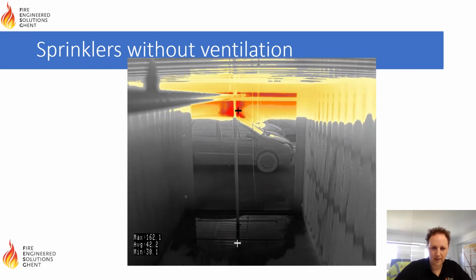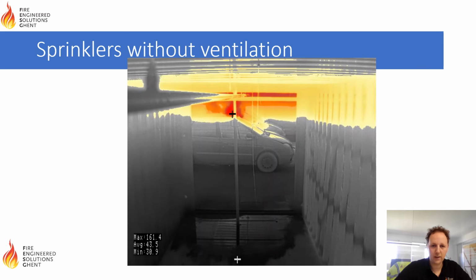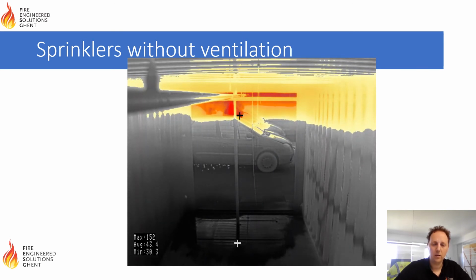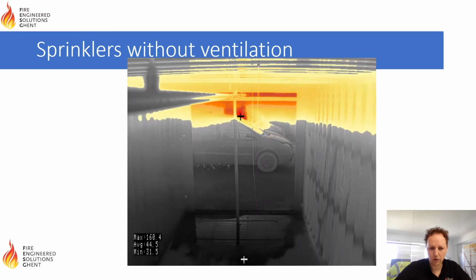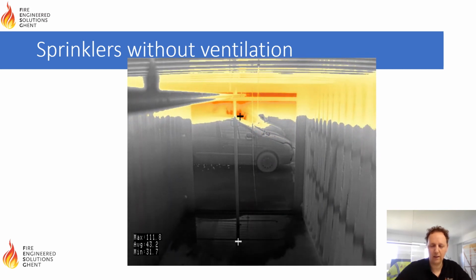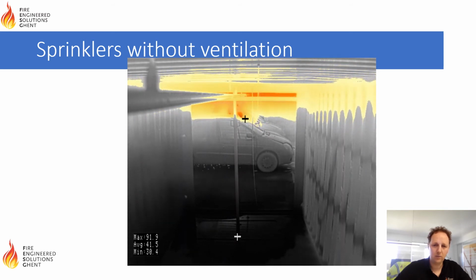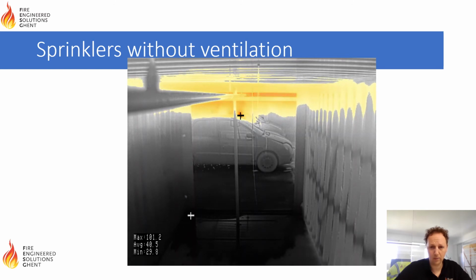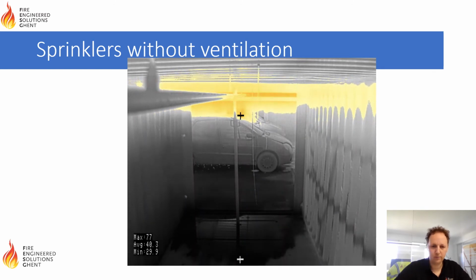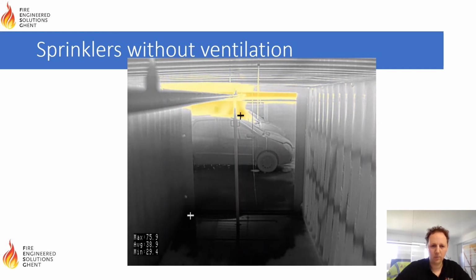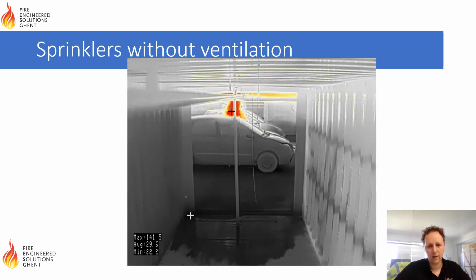And at around this stage, the second window, so the one of the passenger seat, will break. You see here the debris, and little time after the breaking of the window, we'll have the sprinkler system activate. So if you look at the temperature, you can see that at this time the sprinkler has activated, the heat reduction takes place, or the cooling takes place, and in a matter of 20 to 30 seconds, you see how the maximum temperature of the smoke coming out of the window of the passenger seat is around 60 degrees. But more importantly, you see that the average temperature is not above 40 degrees. So this was the result of a fire test with sprinklers with no ventilation.